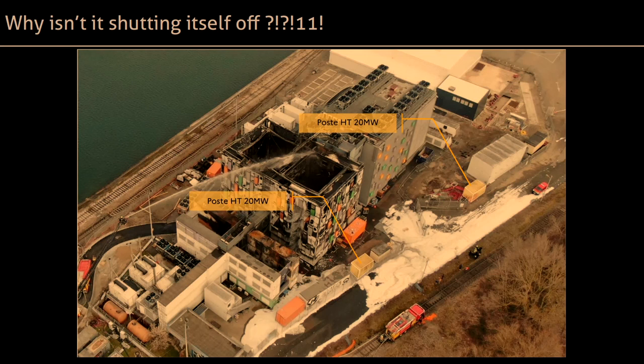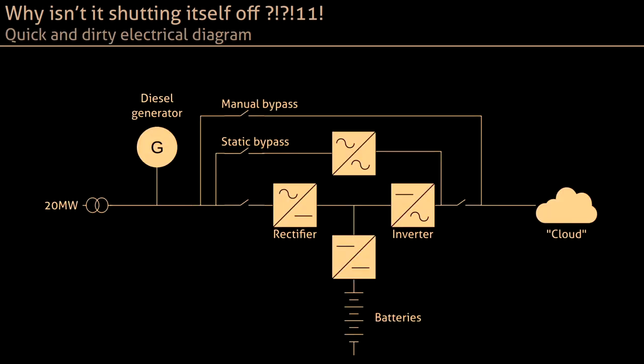Let's recap. We got the uninterruptible power supply with rectifier, inverter, static bypass, and batteries. We turned the diesel generator off. We turned the power supply off. It was still running. Why? Well, of course, you had batteries. So the servers were still running on the lead batteries.